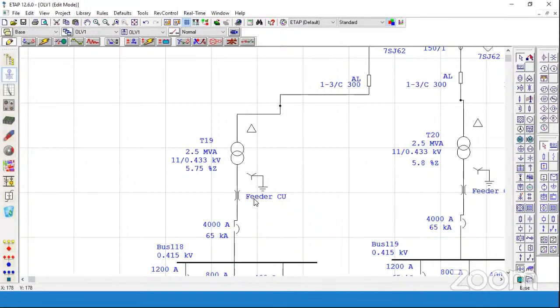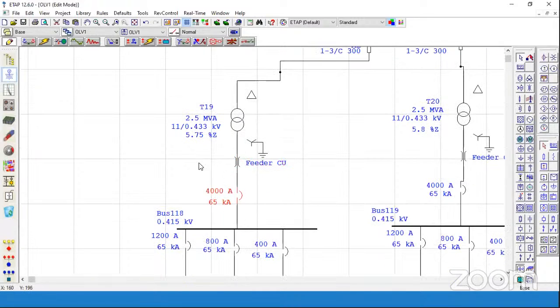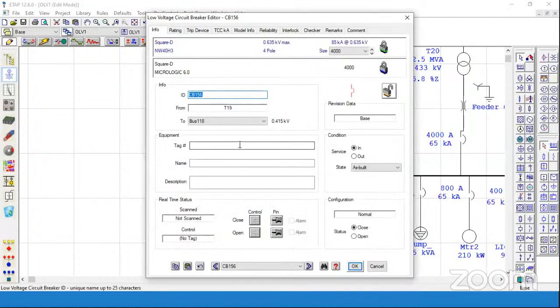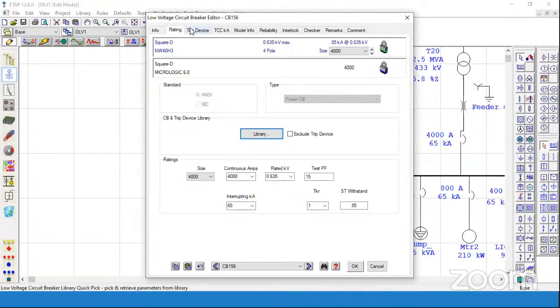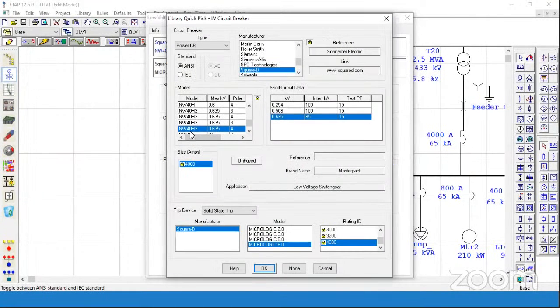Then the feeder bus duct will be there, which will feed the MCC or LT section. This is the LV circuit breaker, low voltage circuit breaker, which has an inbuilt trip unit, meaning release feature, which will work for protection. It will protect the system from certain faults. So this is the trip device we can select from this library. For Square D, I have taken the NW40 model with a Micrologic trip unit. Its rating is 4000 ampere.